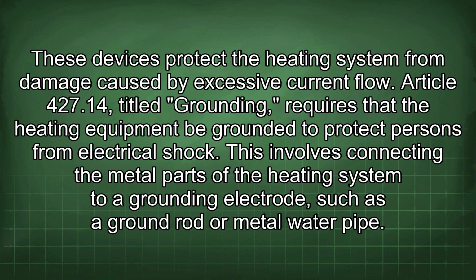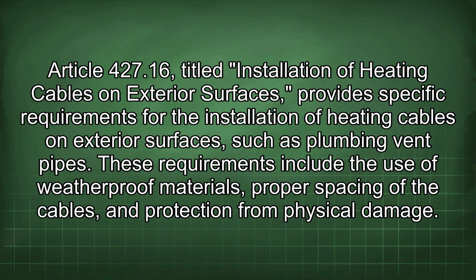Article 427.14, titled Grounding, requires that the heating equipment be grounded to protect persons from electrical shock. This involves connecting the metal parts of the heating system to a grounding electrode, such as a ground rod or metal water pipe. Article 427.16, titled Installation of Heating Cables on Exterior Surfaces, provides specific requirements for the installation of heating cables on exterior surfaces, such as plumbing vent pipes. These requirements include the use of weatherproof materials, proper spacing of the cables, and protection from physical damage.